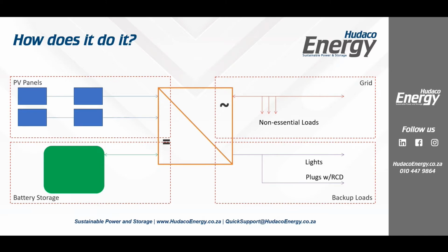Now, we're still looking at the basic introductory training, but that's a great question, because imagine I had a load that I never, ever wanted to run on PV or batteries or anything like that. Okay, yeah. For whatever reason. Then I could actually move my CT to here, and I could put that particular load here. Because what it does is it looks at the current here, and at the moment we set 0 export, or what we call feed-in limitation, it will not export past that CT, even though everything on the load side, on the inverter side of that CT, will be fed so long as our voltage is present. In other words, so long as grid is present, it will continue to feed them.